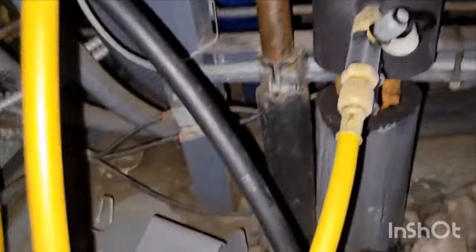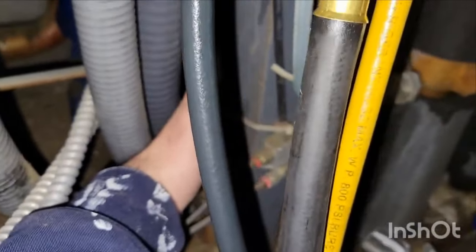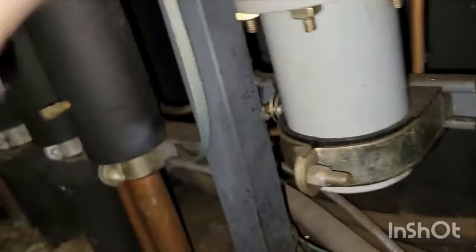Now, from here, I'm gonna touch some other things. As I mentioned earlier, the oil line. Now that the oil is flowing, oh, that's warm. That's nice and warm now. Okay, I know that's okay now. That oil line is all right. It's feeding oil. Okay, I wanted to check to make sure that I was doing that. Still don't have any oil in the reservoir, so we're gonna leave it longer. But is this warm? This isn't gonna be as warm, but right here, that's pretty warm because this goes back to the oil separator. I just want to make sure. Does it seem to be all right?